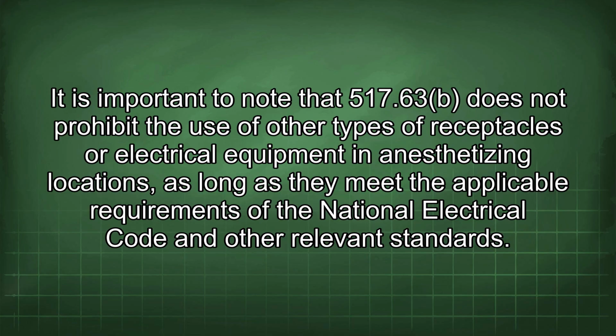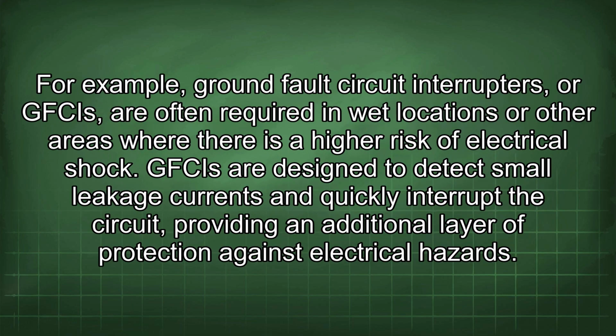It is important to note that 517.63 does not prohibit the use of other types of receptacles or electrical equipment in anesthetizing locations, as long as they meet the applicable requirements of the National Electrical Code and other relevant standards. For example, ground fault circuit interrupters, or GFCIs, are often required in wet locations or other areas where there is a higher risk of electrical shock.